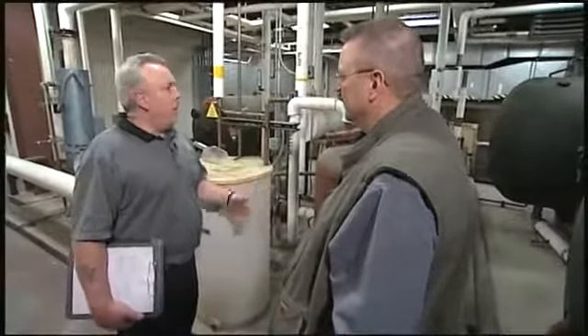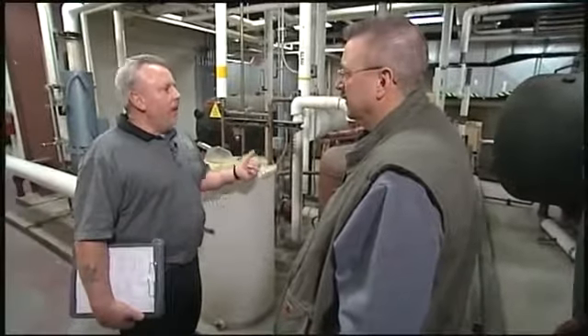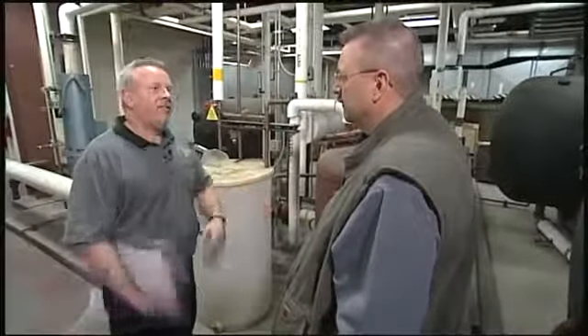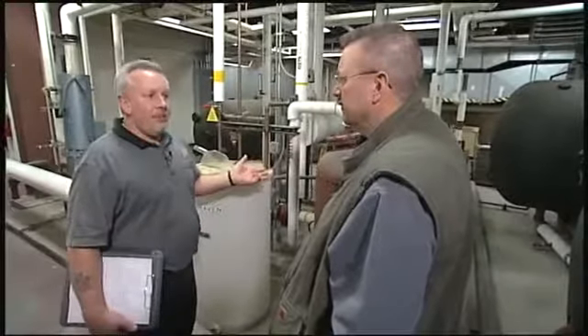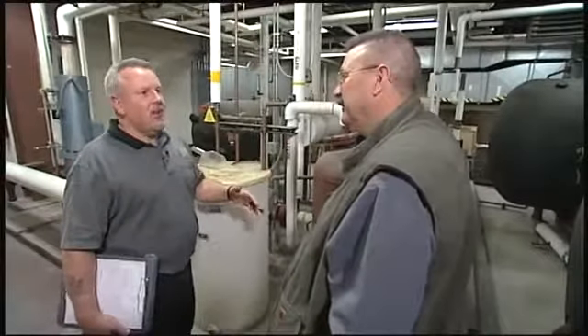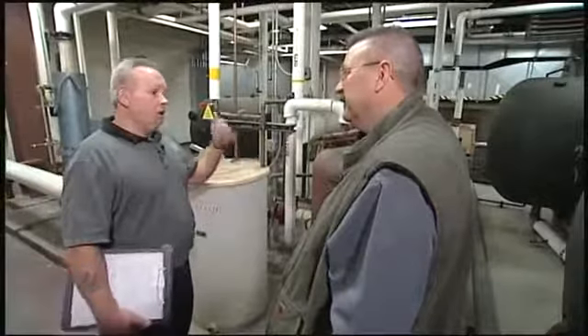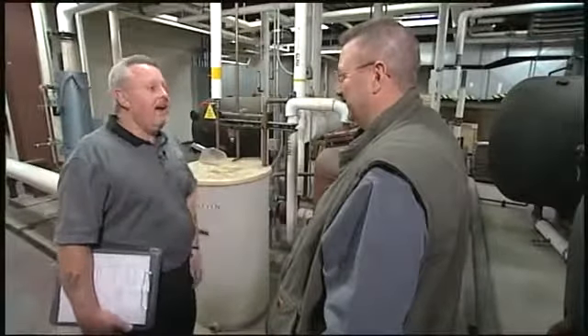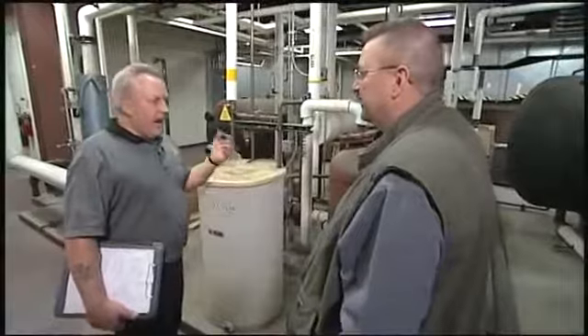Things are altered. For example, recently we had a place where they added a coffee maker. Someone came in, they remodeled an office a little bit, wanted something somewhere else. And then there were complaints of how the coffee tasted, and it was discovered when they looked that the vendor went up in the ceiling and tied into a 3/4 copper line. That wasn't a cold or hot water line. That was a hydronic heating line with chemicals, with antifreeze. Glycol or antifreeze, yeah. And so luckily they identified that in a hurry, and nobody got significantly sick or ill.